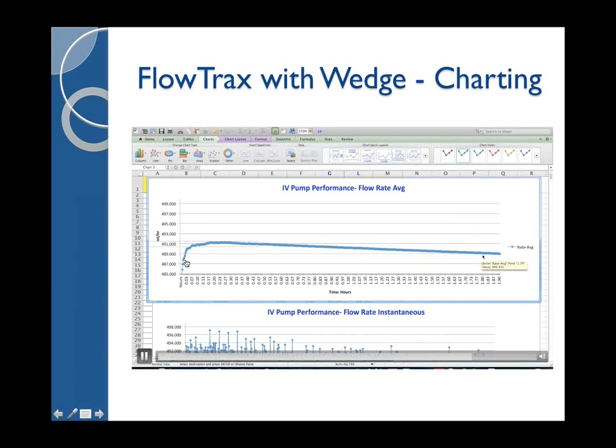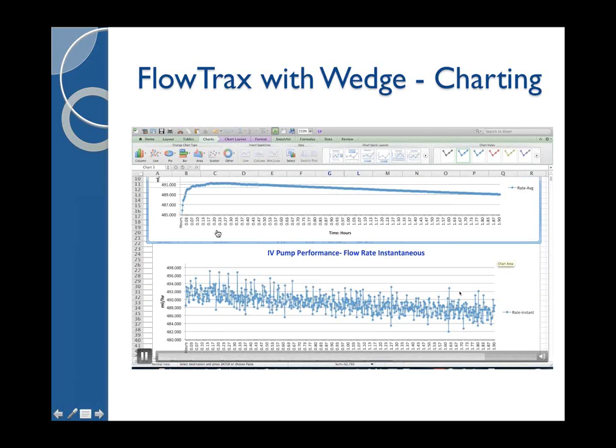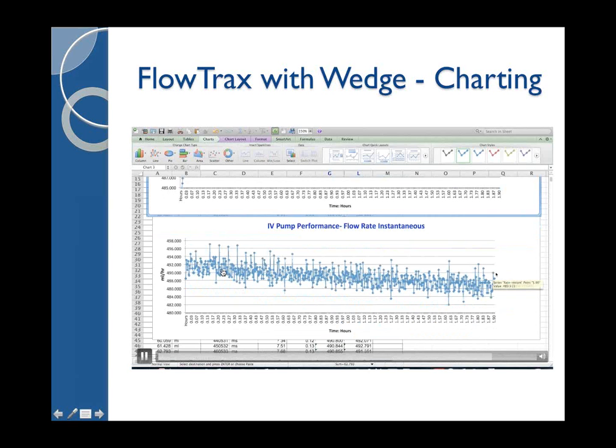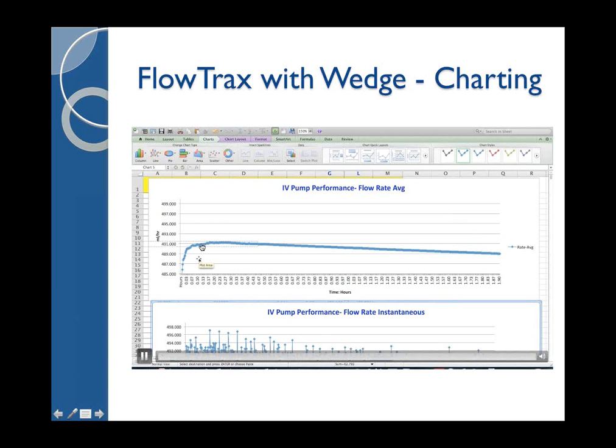Notice that the flow rate average declines over time, both in the average and in the flow rate instantaneous analysis of the IV pump. And we'll talk about the reason for that here in a minute. But you can see that it starts out kind of slow. The pump reaches its expected rate, and then over time it's declining, and it actually drops almost by 1%.